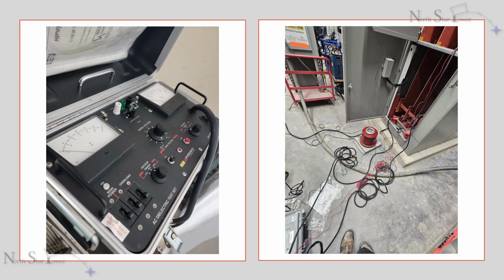High-pot testing is a high-voltage insulation test that simulates extreme stress to ensure the breaker's insulation can withstand fault-level voltages. High-pot testing can be done with AC or DC, depending on field conditions. If the insulation allows any current to leak through, the breaker fails. This test is especially important at higher voltages, where even minor insulation defects can become deadly.